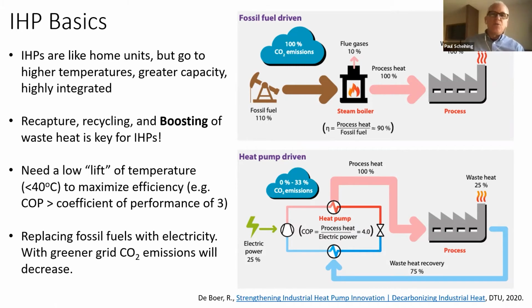Now they're getting up to 120, even hopefully to 160. They're a much greater capacity, they can be megawatt size, and they're usually very highly integrated into the industrial process, which makes them a little more complex. They're recapturing, recycling, and boosting waste heat. And generally what you want to do is find low lift applications, around less than 40 degrees C.